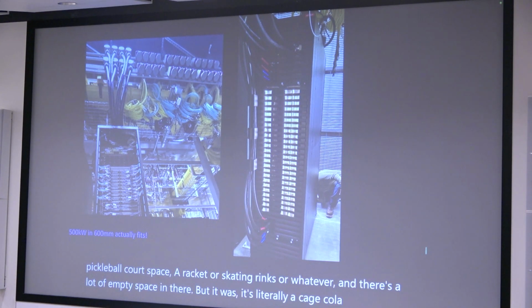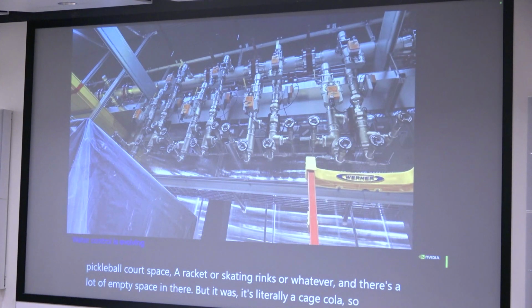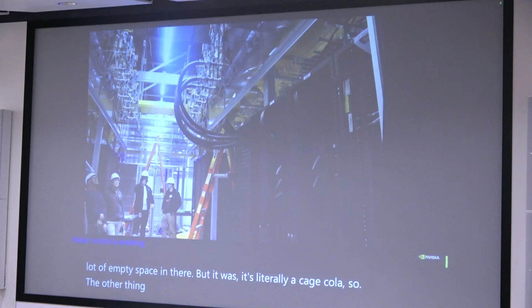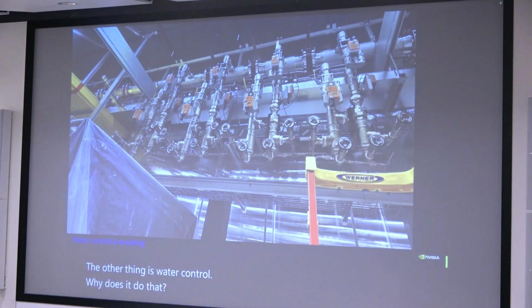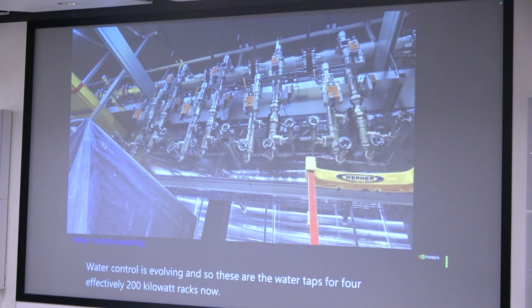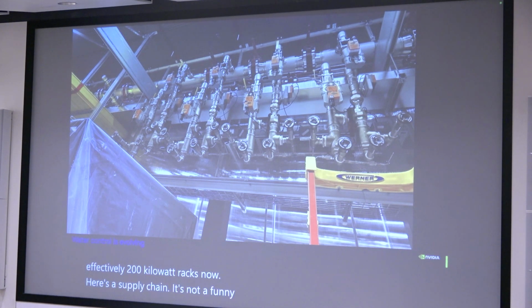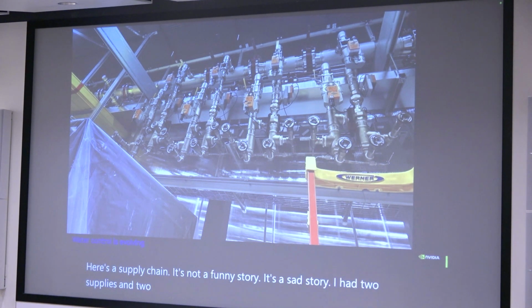So the other thing is water control. Water control is evolving, and so these are the water taps for effectively 200 kilowatt racks. Now here's a supply chain—it's not a funny story, it's a sad story. I have 2 supplies and 2 returns for each rack, not to feed 2 manifolds, but the FD83 connector, which is a hot plug connector with a valve already into it.